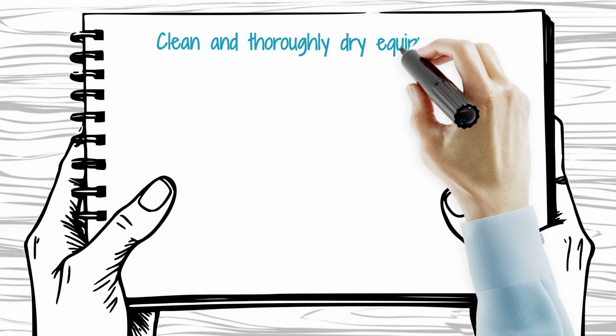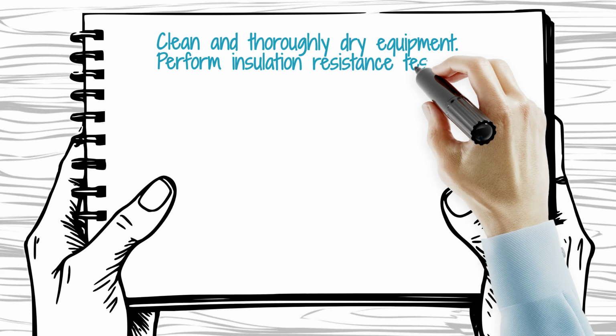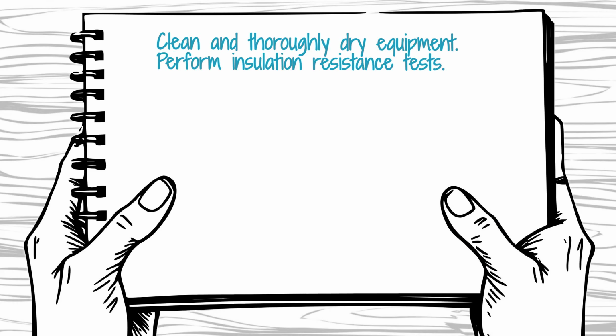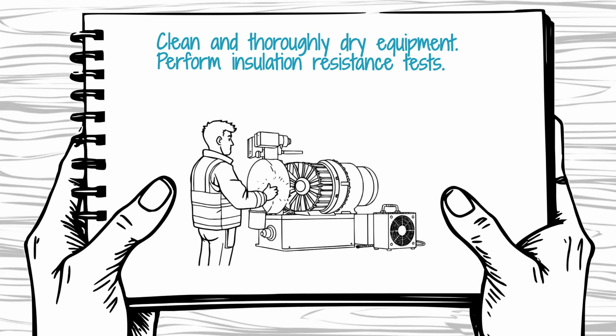The fifth step is drying and cleaning. For critical or high-voltage equipment like motors or switchgear, cleaning must be done using specialized non-residue cleaning agents. The equipment must then be dried completely. Industrial dehumidifiers and warm air circulation should be used to remove internal moisture.